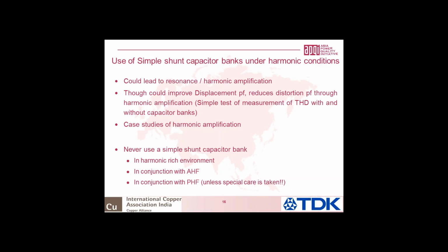And recently, I was traveling in the southern part of the country. I came across at least 3 or 4 classical cases where a customer had simple capacitor banks, which were installed maybe 10 years back because he wanted to get an incentive for power factor. Now the same utility is penalizing him for the increase in harmonics, but he doesn't know what to do. He's got a simple capacitor bank, almost 400 kVAR, and his harmonic distortion was very high.